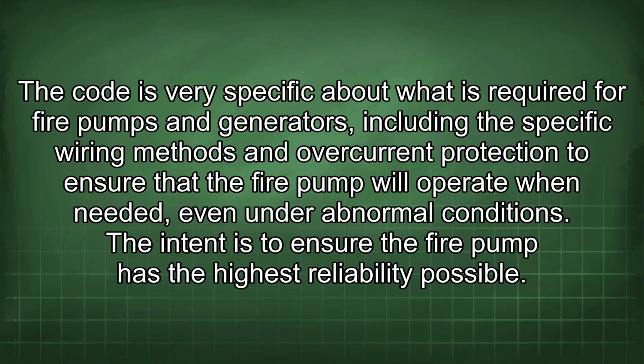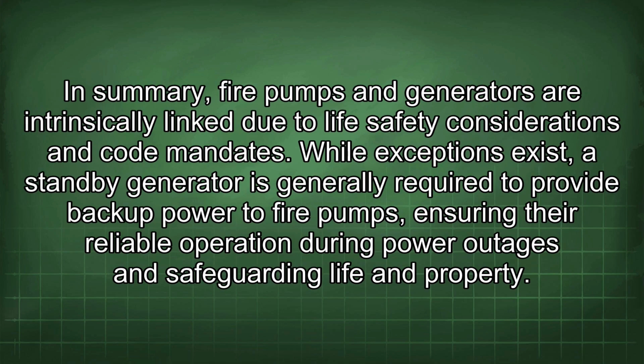The code is very specific about what is required for fire pumps and generators, including the specific wiring methods and overcurrent protection to ensure that the fire pump will operate when needed, even under abnormal conditions. The intent is to ensure the fire pump has the highest reliability possible. In summary, fire pumps and generators are intrinsically linked due to life safety considerations and code mandates. While exceptions exist, a standby generator is generally required to provide backup power to fire pumps, ensuring their reliable operation during power outages and safeguarding life and property.